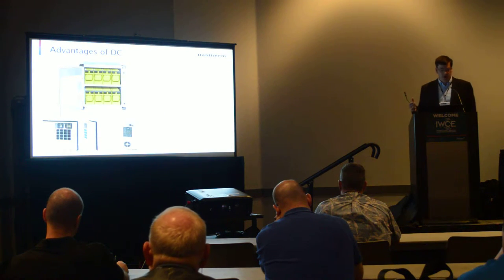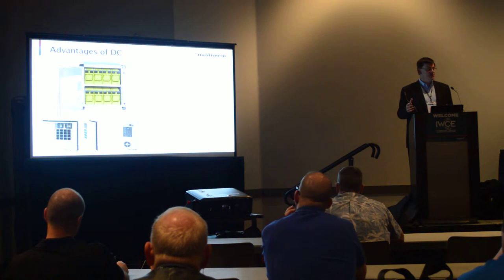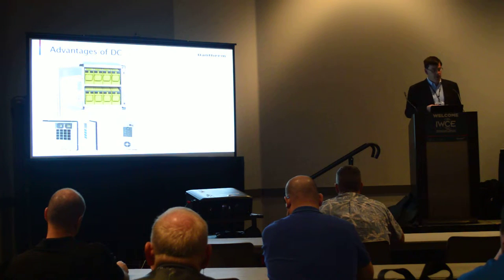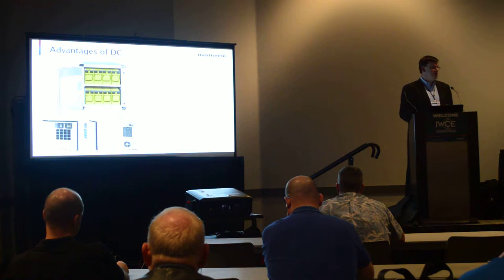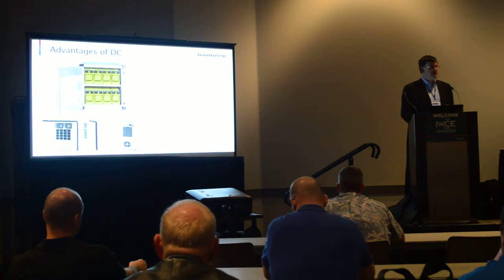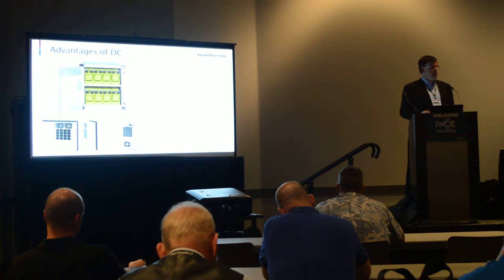This is a picture of a DC air conditioner on a battery cabinet — you can imagine this inside your shelter where you're trying to maintain battery temperatures in a dual zone cooling solution. Adjustable set points and all the features you need from a normal air conditioner are available with a DC air conditioner. Compared to the TEC thermoelectric solution, which is the other prevalent active solution, the DC is much more energy efficient, while TEC is fairly limited in cooling capacity and efficiency.